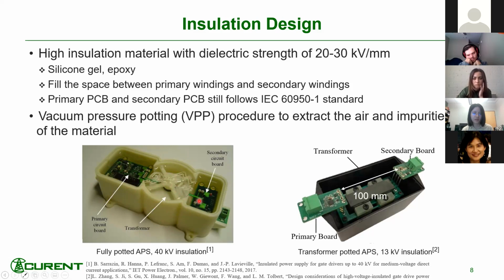Because this material has to fully cover the whole transformer, you can also put the material onto the primary and secondary board to enhance the insulation. Otherwise, you can just pot the windings, so only the windings are covered in silicone gel, but the PCBs are exposed in the air. In this case, if the PCBs are exposed in the air, it will still need to follow the requirements shown on the last page. So it's 100 millimeter apart to support this 13 kV insulation.